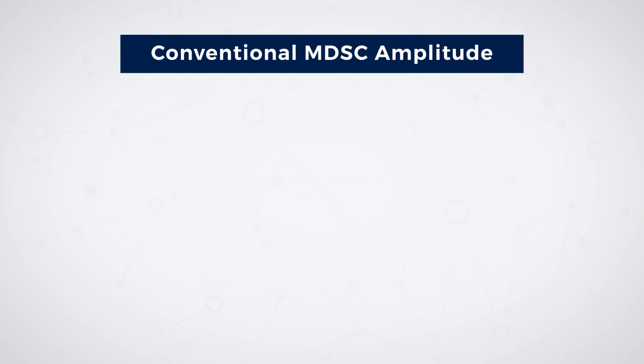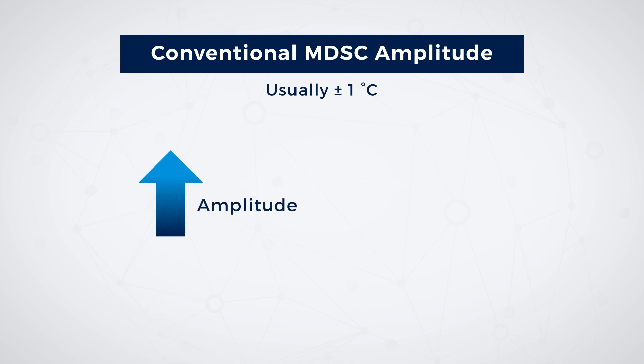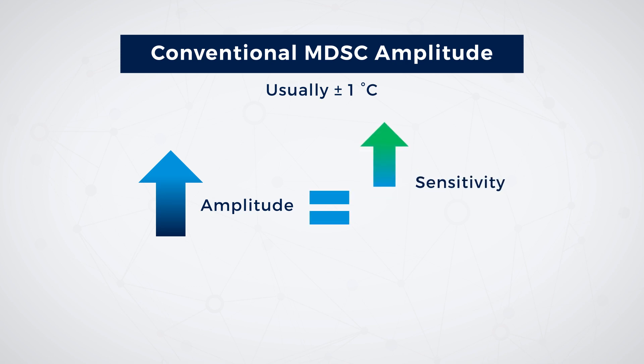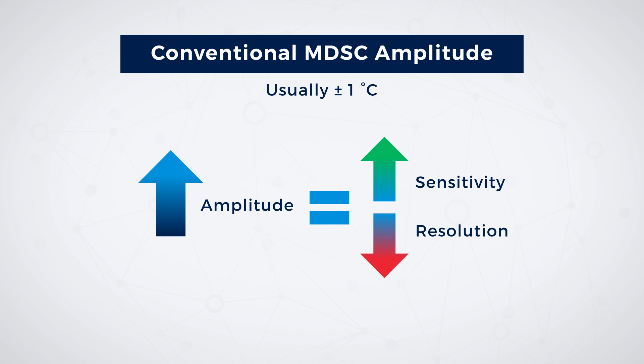The modulation amplitude is most commonly set to plus or minus one degree Celsius for conventional MDSC experiments. Larger amplitudes will result in greater sensitivity, which may be helpful in identifying hard-to-observe glass transitions. However, if the amplitude is too large, there may be a loss of resolution. A large amplitude may also adversely affect the linearity of the heat flow response, resulting in an irregular temperature modulation.